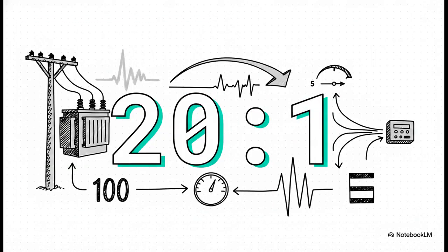Building on that, let's look at the transformer ratio. Imagine you have a primary current of 100 amps and a secondary current of 5 amps. Your transformer ratio is 100 to 5. We just simplify that math by dividing both sides by 5, which gives us the 20-to-1 ratio you're seeing right here. It's that simple. It perfectly illustrates how that step-down proportion actually functions in the real world to scale down massive, dangerous currents into manageable, readable levels.